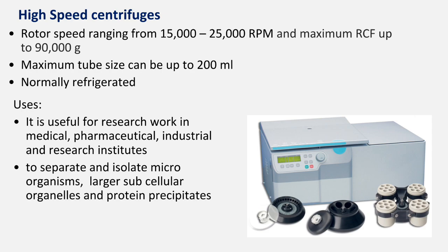And in these centrifuges, most of the time they use angle head rotors. Here you can see the cups with low resistance and angle head, which we can't change. In some we can use a swinging head. So when we operate the centrifuge, it will swing from the vertical position to the horizontal position.